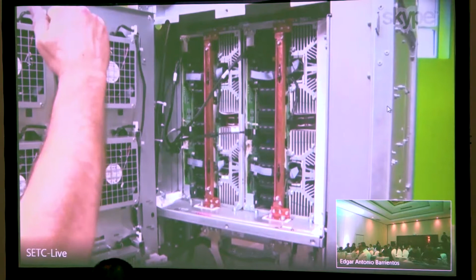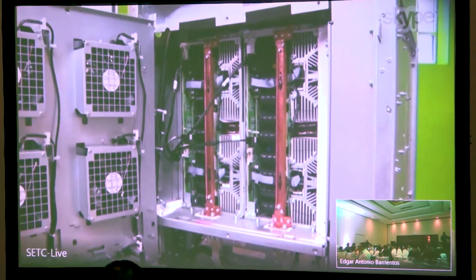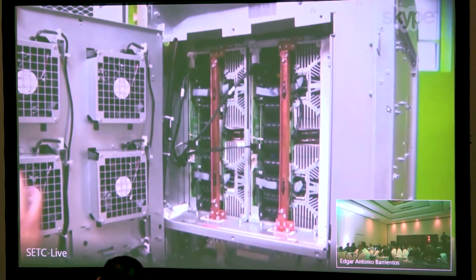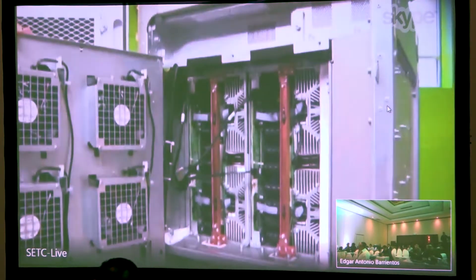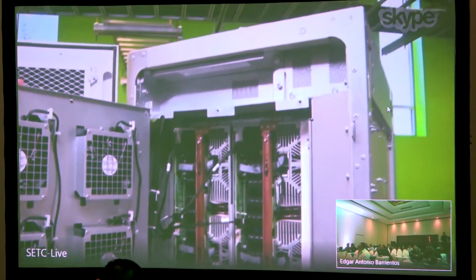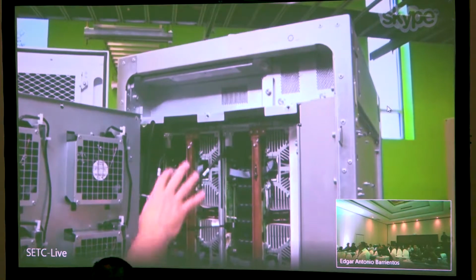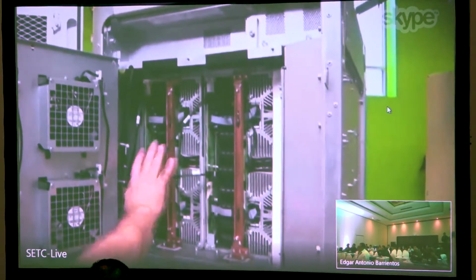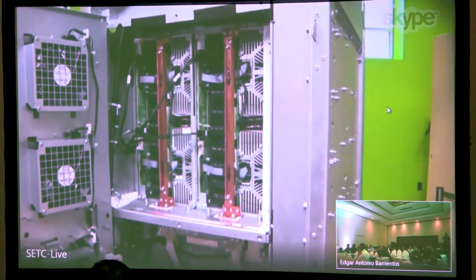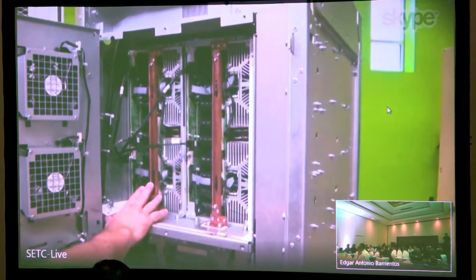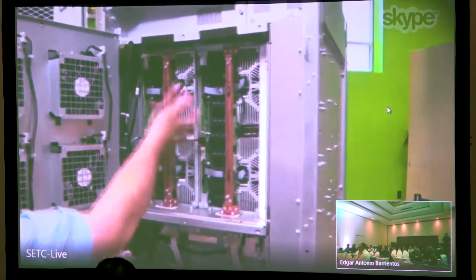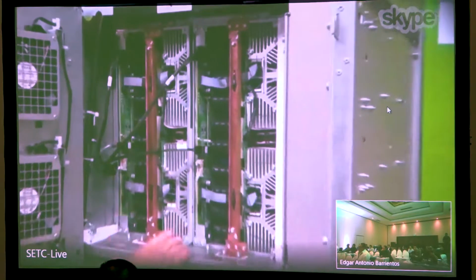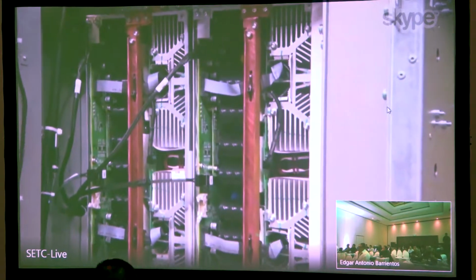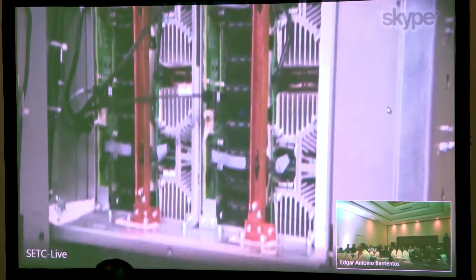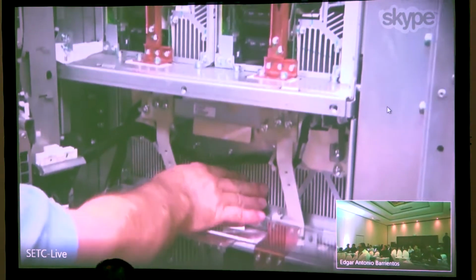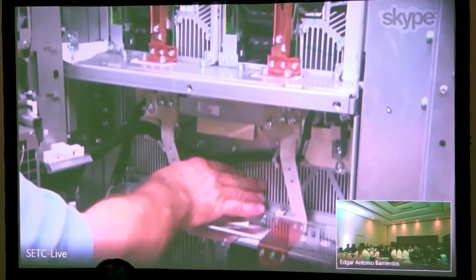Going through the parts of the cabinet, at the very top we have the controller and the power supply for the cabinet controller. Moving down, these are the power blocks for the UPS. We need two per phase, with copper and fiber connections going up to the main controller. Below that is the rectifier, rated at 250 kilowatts.